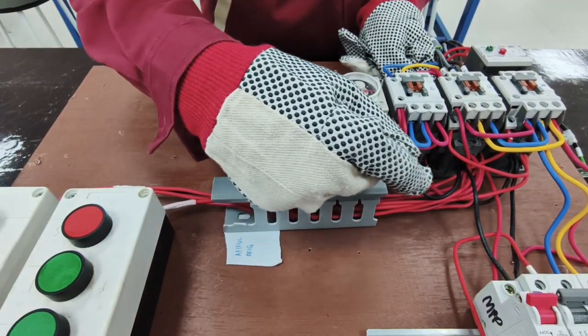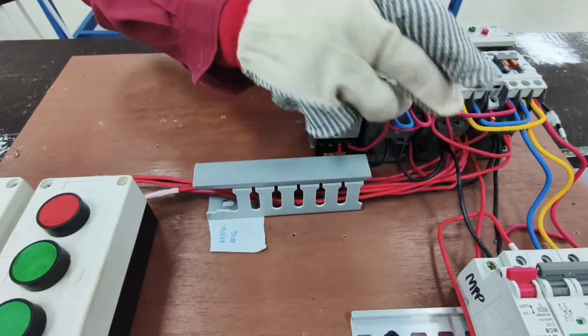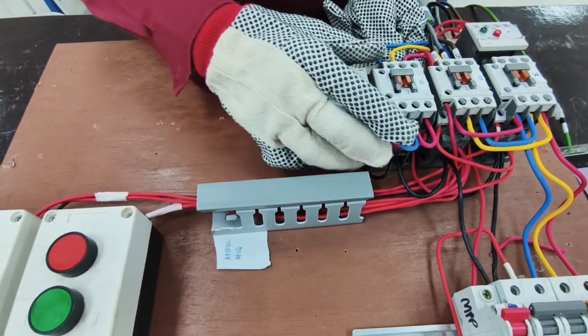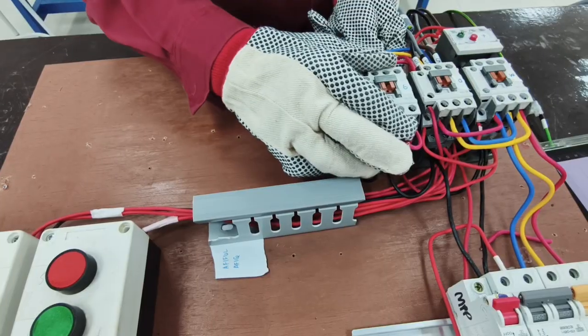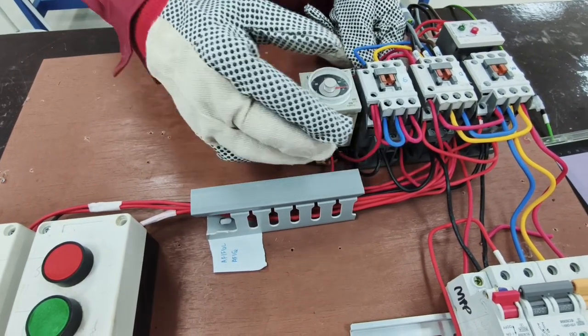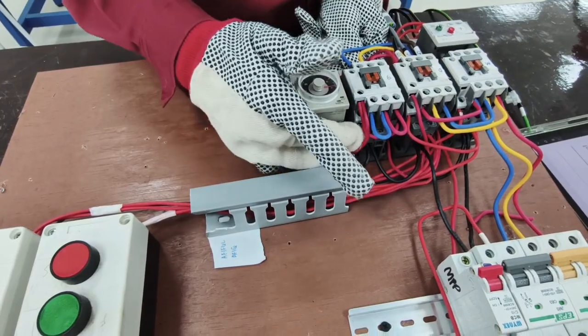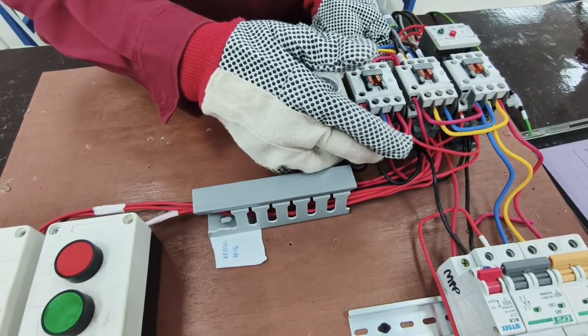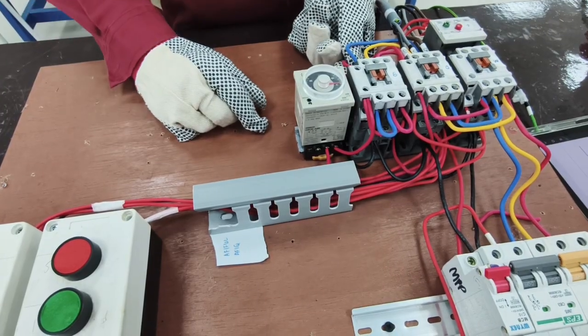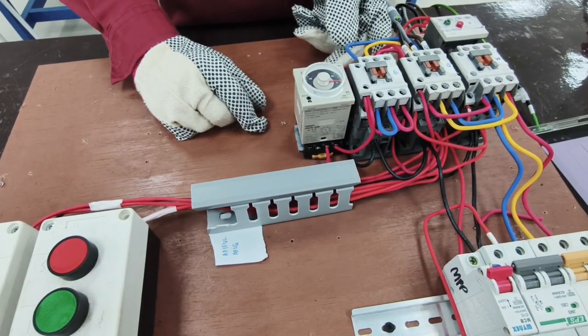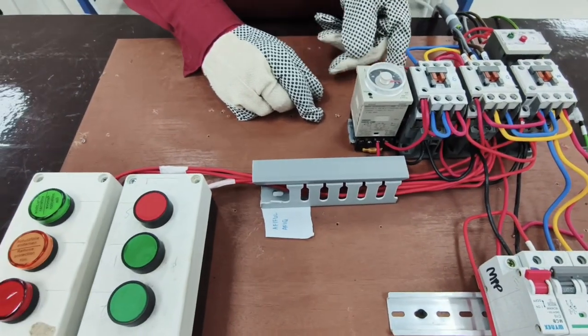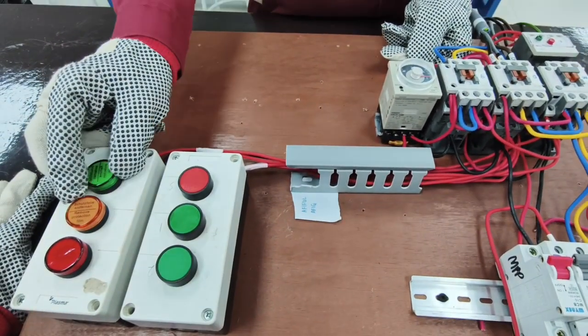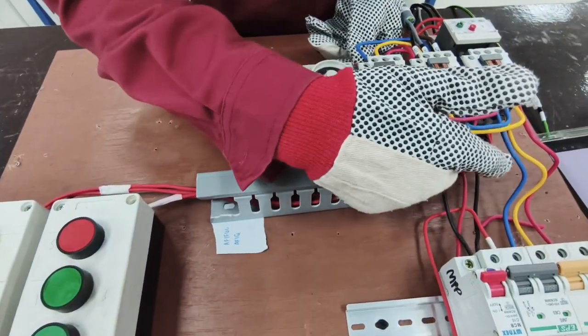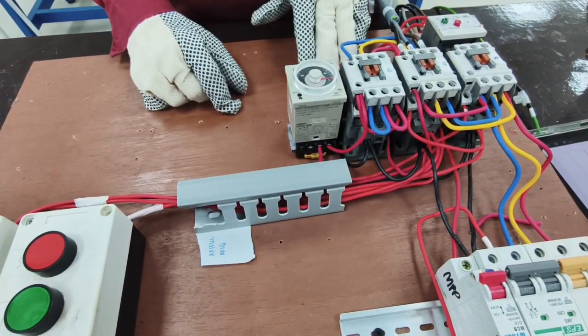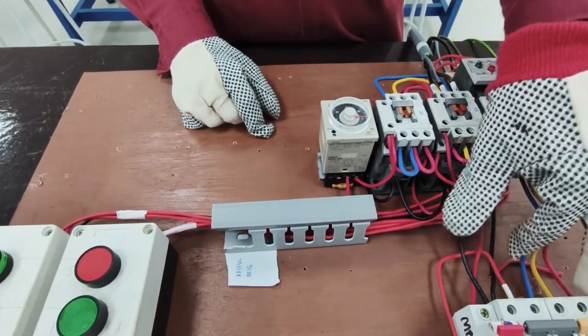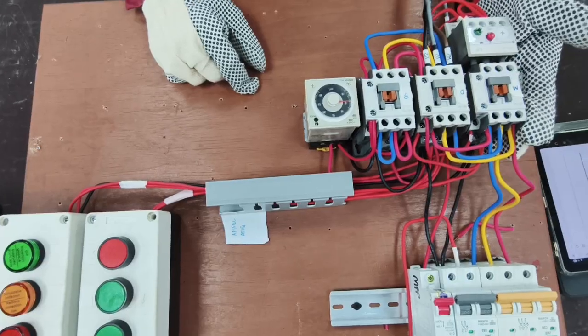Then from the outgoing of our latching, we connect to the star contactor, but the normally closed contact. This is also for the interlock mechanism. Then it will go to point number 31. From point number 31, it will go to the green indicator lamp and to A of the delta contactor. And then all the neutrals loop and meet at the same point. So that's all for the control circuit.